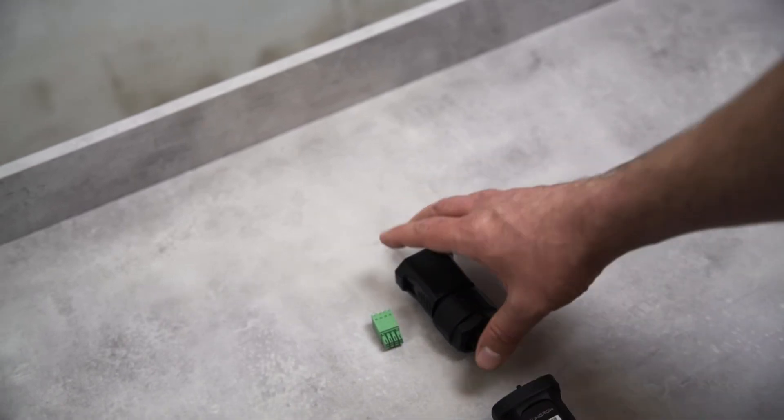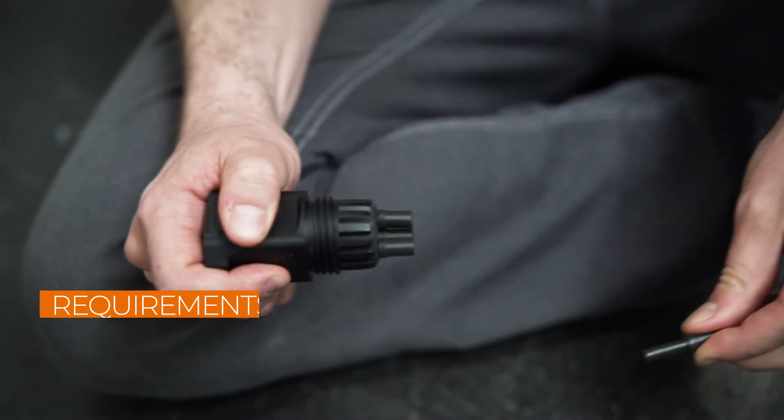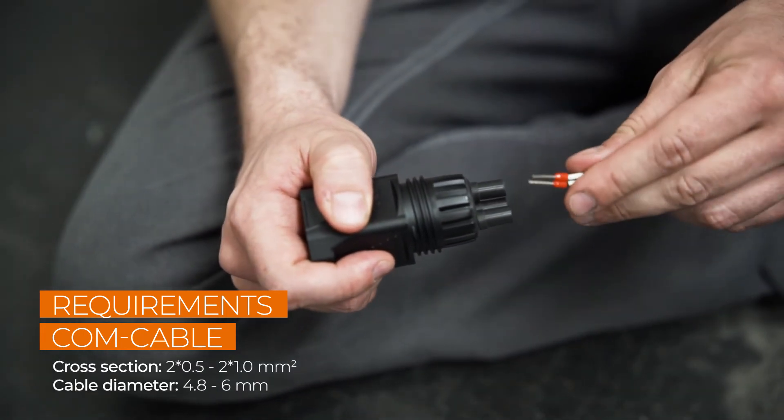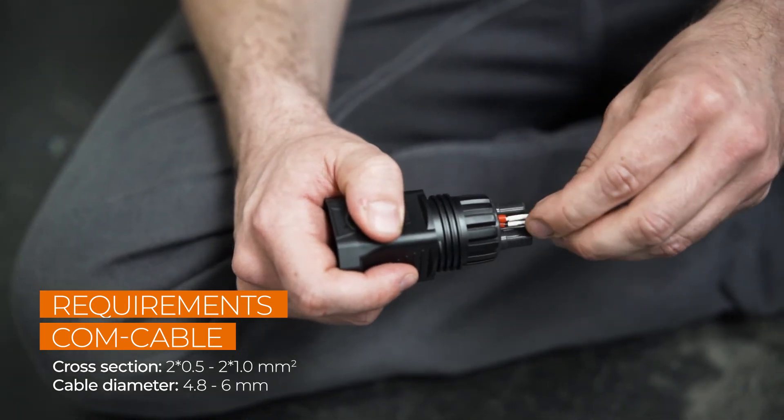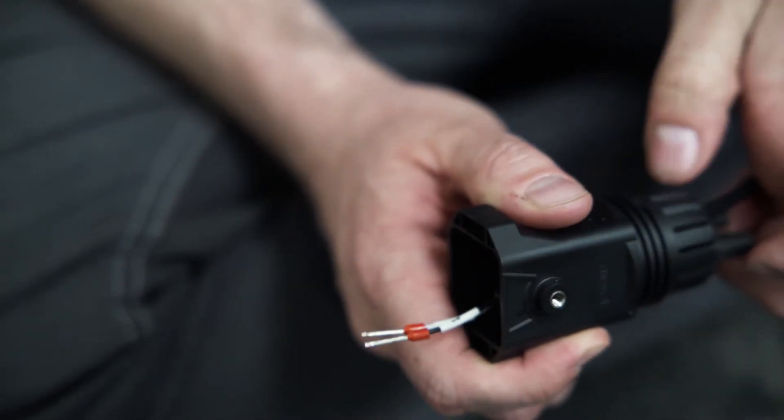In the next step, we will connect the energy meter to the communication port of the inverter. Remove approximately 4-5 cm of the cable sheath of the communication cables. Then strip approximately 7-10 mm off the inner cables. If necessary, you may have to fit the cables with end sleeves before you push them into the plug.